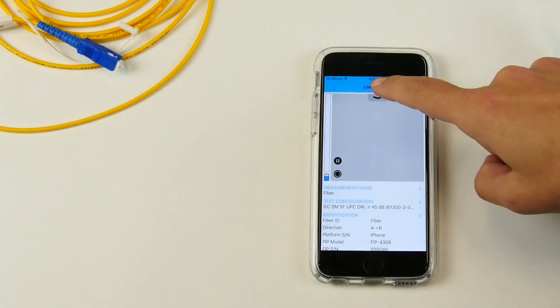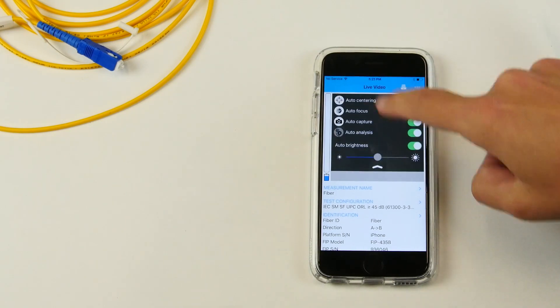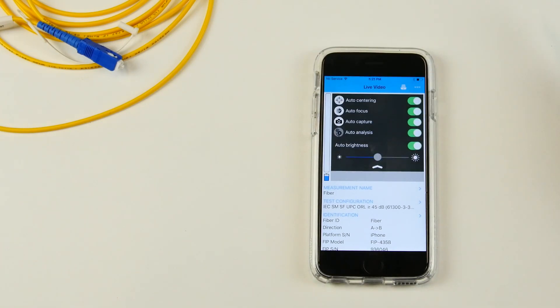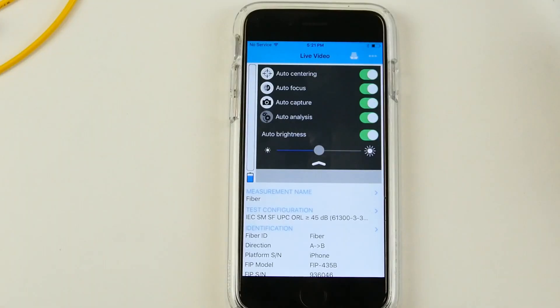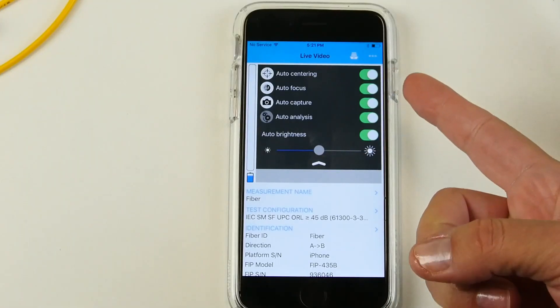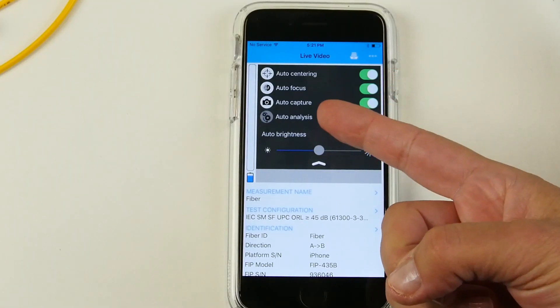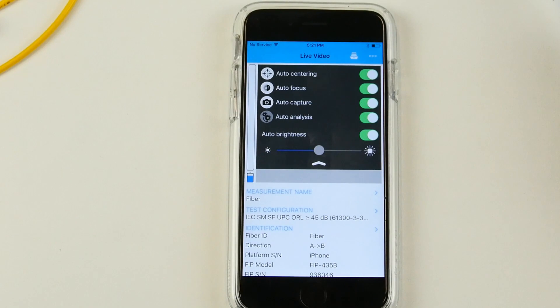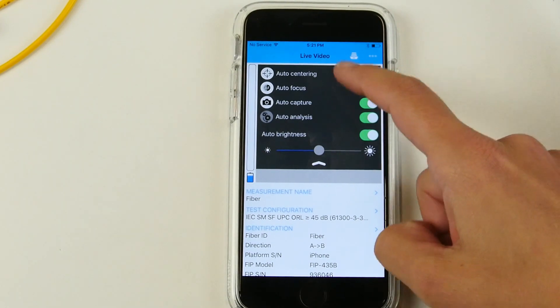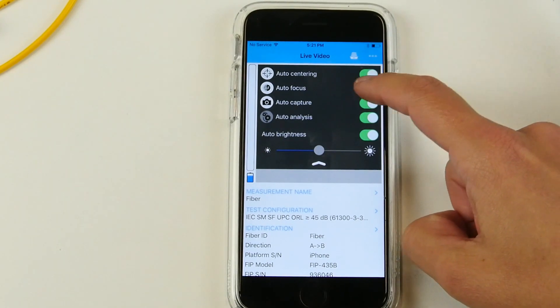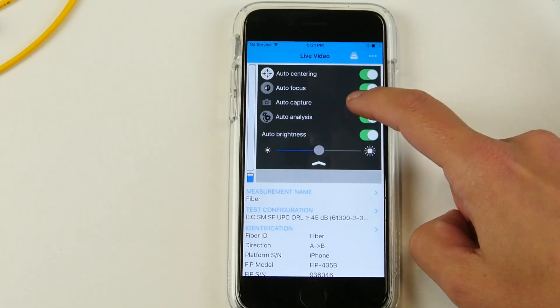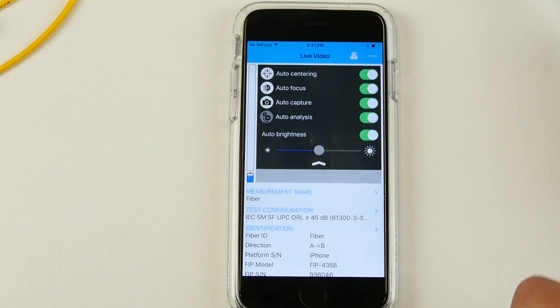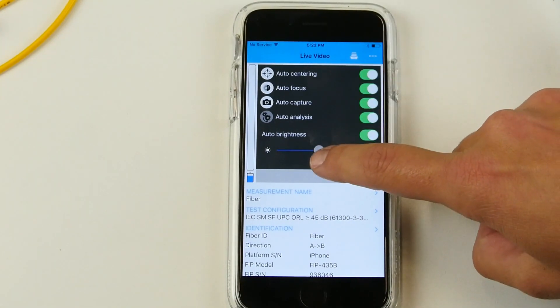You can also configure the amount of testing that you want to do with your wireless probe. So, it is set as of now to auto-center, auto-focus, auto-capture, and auto-analysis, but you can deactivate one or two as you see fit. We're just going to leave them in for now.